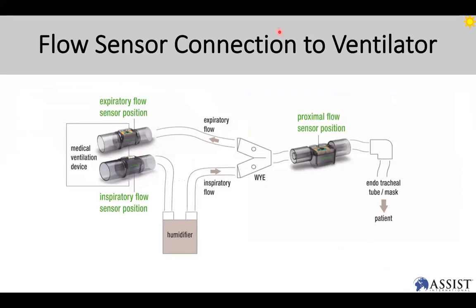Ah, yes, okay. So the proximal flow sensors allow for a better reading on the flow rates to the patient. The general idea of having as many sensors as possible is because the patient circuit can sometimes be very long, especially if you add humidifiers and multiple filters in the circuit. You've got inspiratory and expiratory flow sensors that allow you to measure flow and pressure close to the ventilator, but the patient's still on the other end of the circuit. And so a proximal flow sensor allows you to get better readings right at the point where the air enters and exits the patient airway. Okay, thank you.